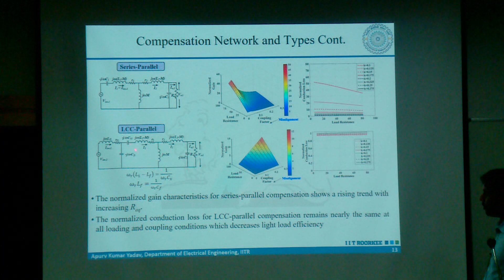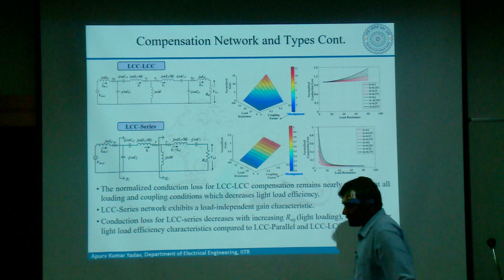Then comes LCC. Again with LCC, as load resistance reduces, meaning light load condition, the conduction loss increases, because the coil currents remain the same in the LCC network. If we see the LCC series system, with load there is no change in the voltage gain, so it has a load independent voltage gain characteristic. In this system, the primary coil currents are constant, but secondary coil currents are load dependent. That's why in light load condition we have some fixed amount of conduction loss, but it is smaller than in the LCC parallel system.